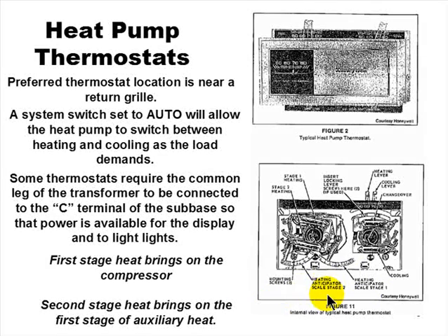Providing the outdoor thermostats have been installed. And another reason you use outdoor thermostats is to avoid peak load. What people do, they treat heat pumps like they were gas furnaces. They come in from the outside on a 20-degree day, and they go in the house, and the house is in setback mode because they've been at work all day, and the house is maybe 60 degrees, 65 degrees, and they go, oh, I got to chill, and they turn the thermostat up to 90. Well, if you don't have outdoor thermostats, when you turn that up to 90, you pulled all the backup heat in. But if you stage it across the outdoor thermostats, then the heat you don't need won't come on until you need it.